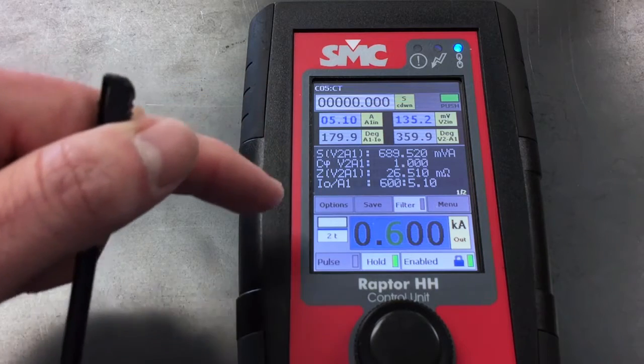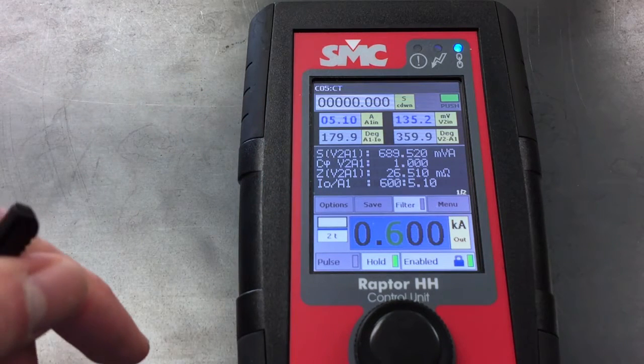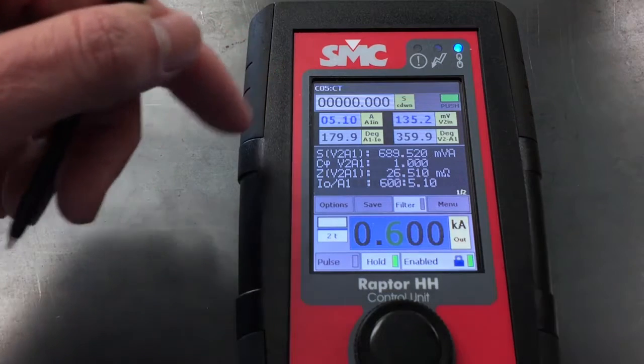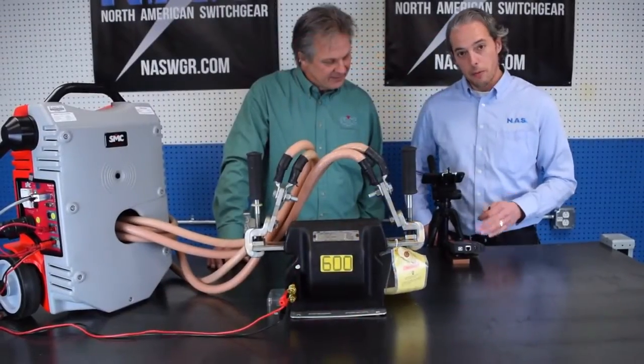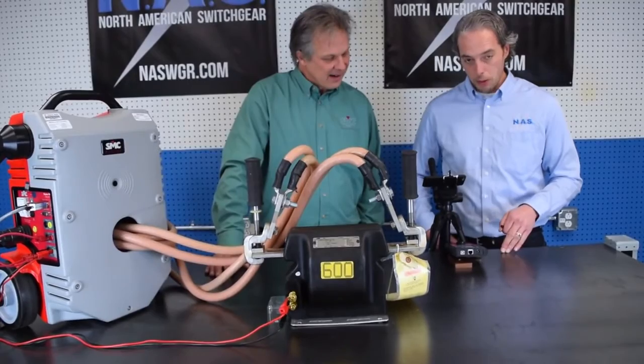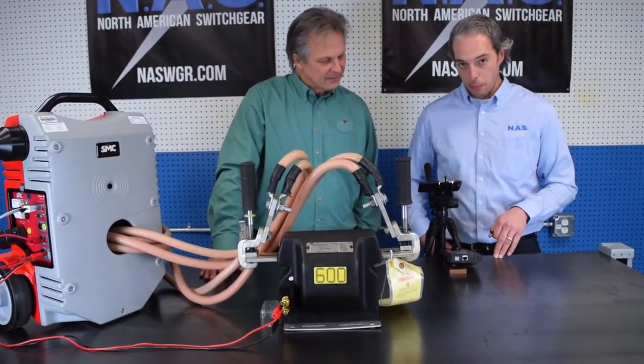You're right on the money. So 600 to 5 is what's showing on here. Your polarity is 179.9 — this is pretty cool. You're good. Yeah, this is great for testing CTs, CPTs, PTs — I'm very impressed with it.